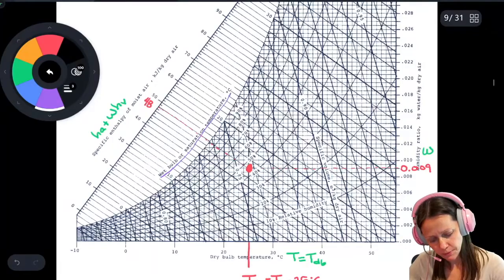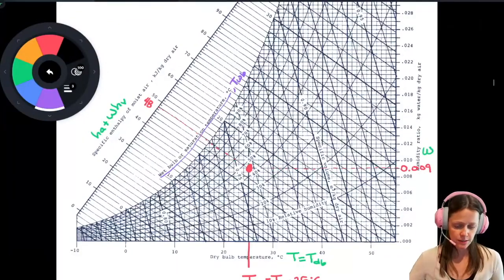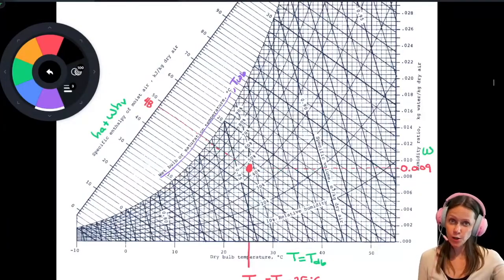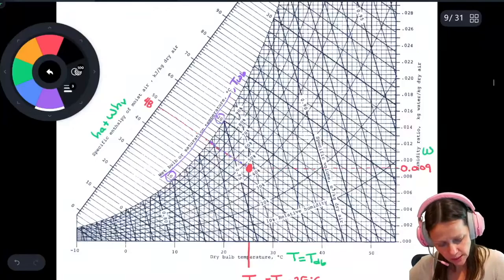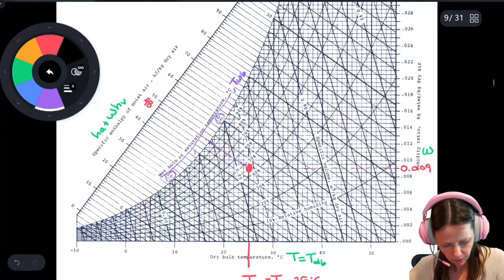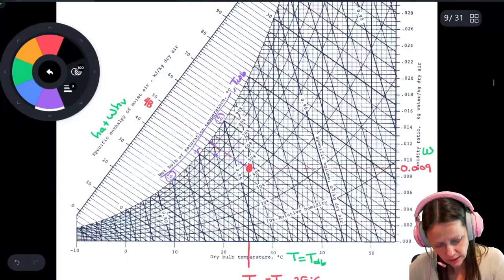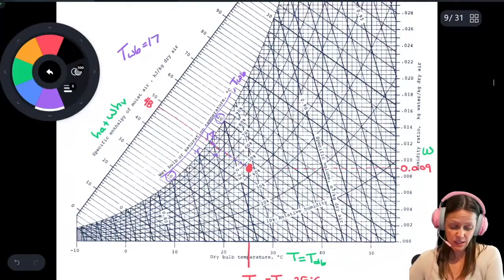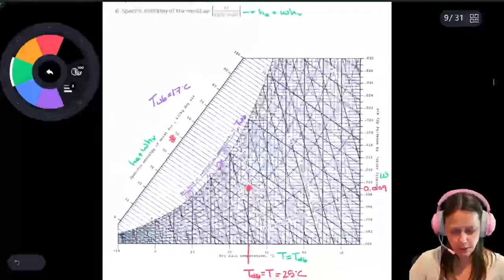In purple, you'll notice your wet bulb temperature — that's the saturation temperature. The lines of wet bulb temperature and the lines for specific enthalpy of the moist air are parallel to one another. Tracing that line up from 25 degrees Celsius at 50% relative humidity, it looks like we would have a wet bulb temperature of about 17 degrees Celsius.